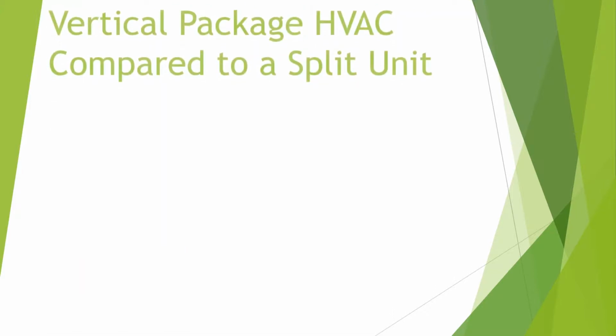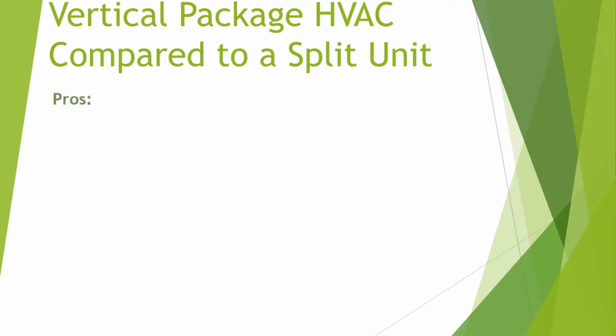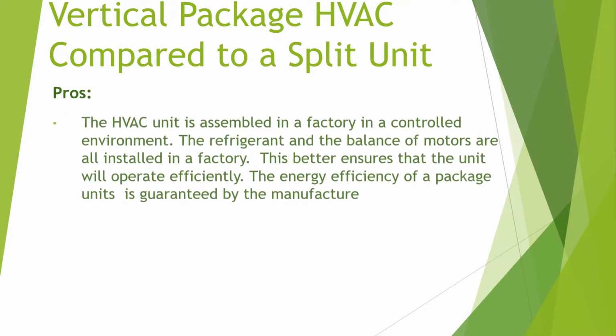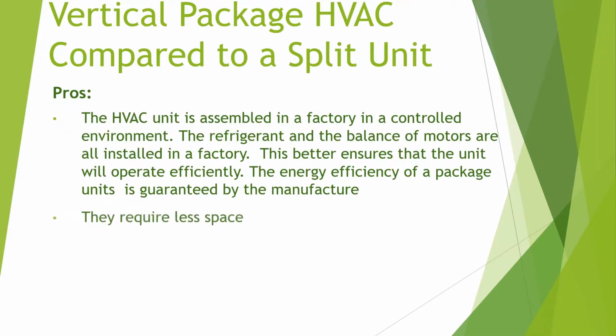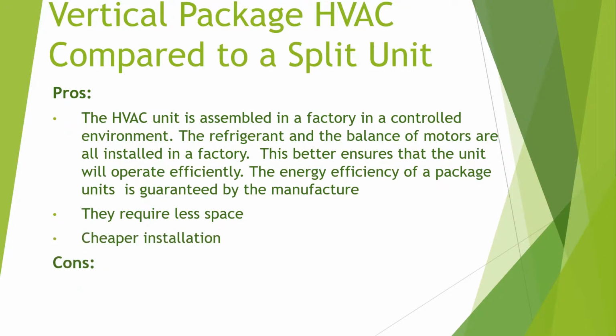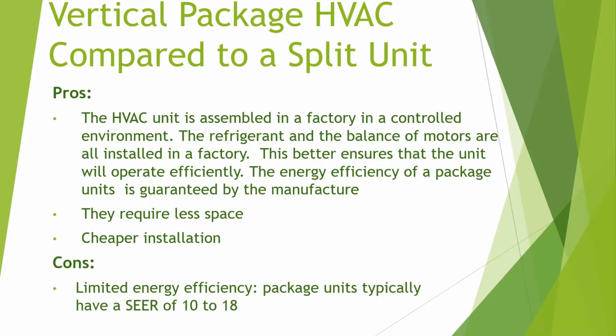Comparing a vertical package HVAC unit to a split unit, the HVAC unit is assembled in a factory in a controlled environment. The refrigerant and the balance of motors are installed in a factory. This better ensures that the unit will operate efficiently. This energy efficiency of a package unit is guaranteed by the manufacturer. They require much less space and overall have a cheaper installation. Negatively though, the package HVAC units have a limited energy efficiency, typically with an SEER of 10 to 18.